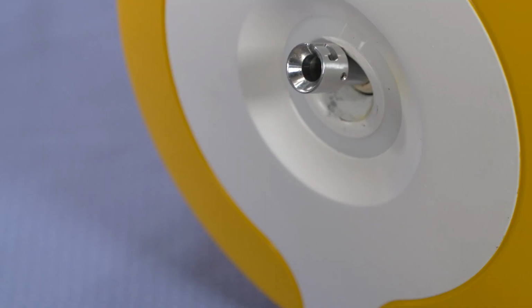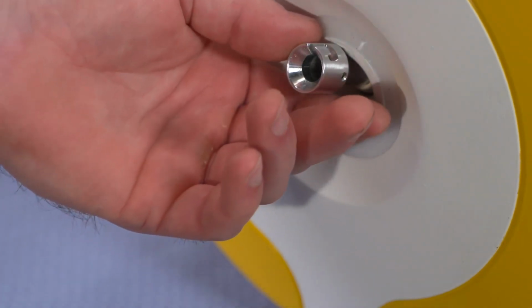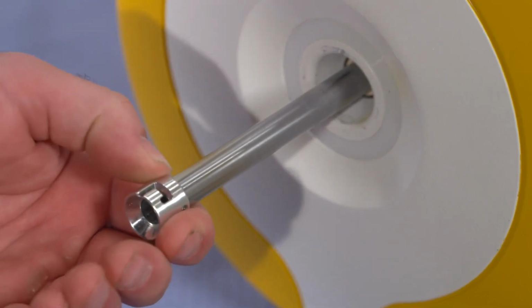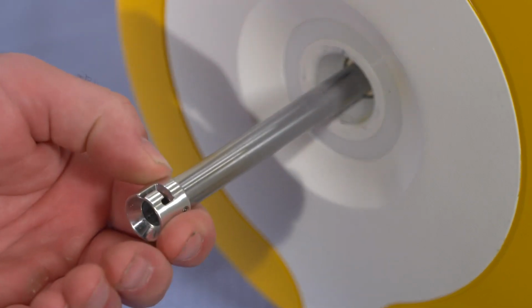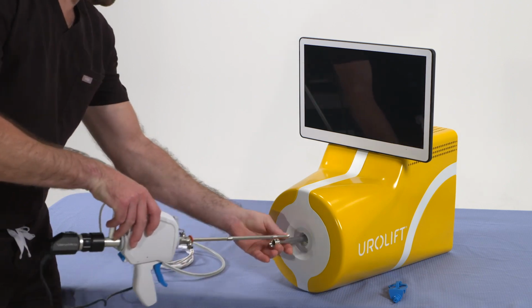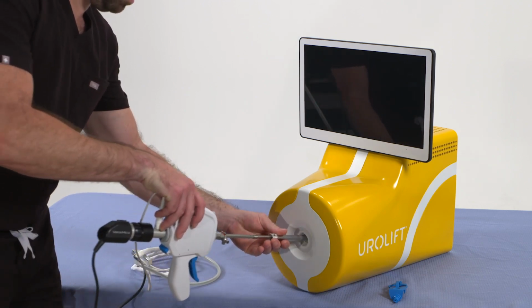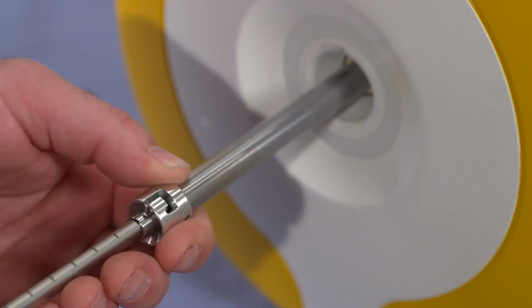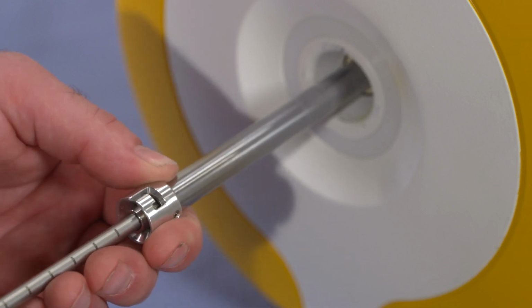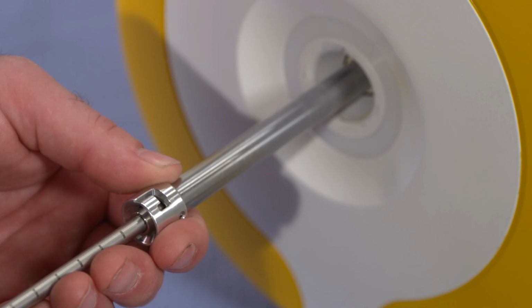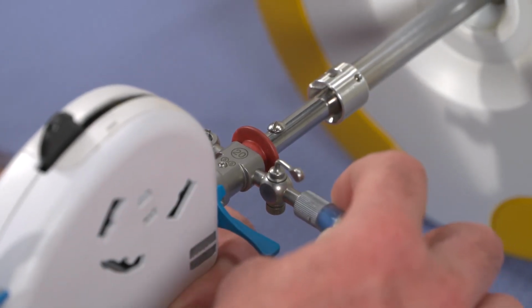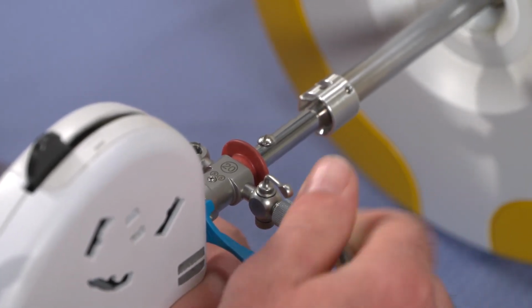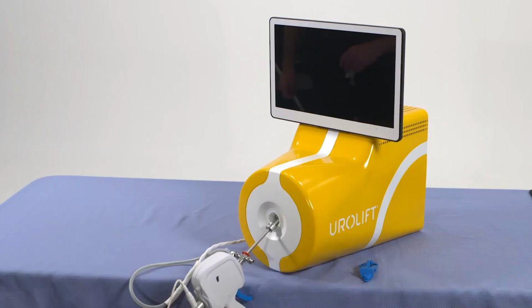Now, while holding the SIM handle, gently grasp the metal stem protruding from the front of the SIM box. Insert the tip of the SIM handle into the stem, while aligning the metal pin with the slot at the top of the SIM box stem. Rotate the handle gently to the right to secure the pin in the slot. Connect the clear tubing to one of the sheath ports on the handle. This completes the setup portion of the simulator.